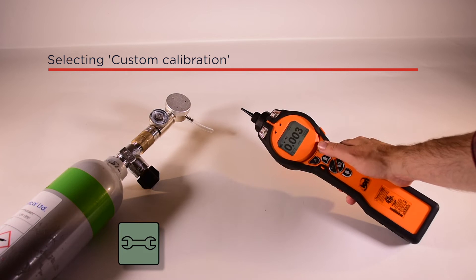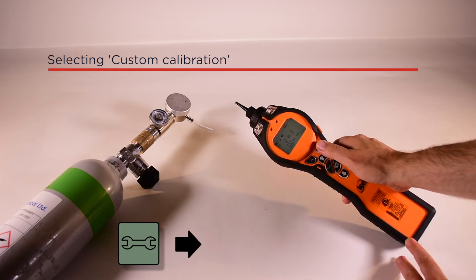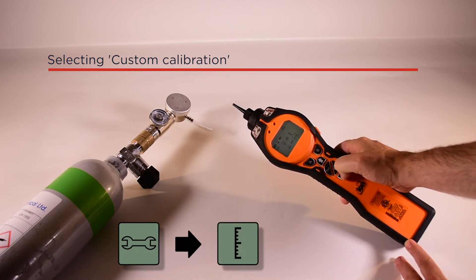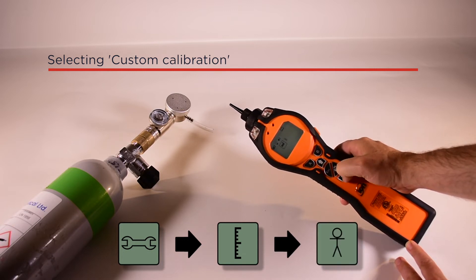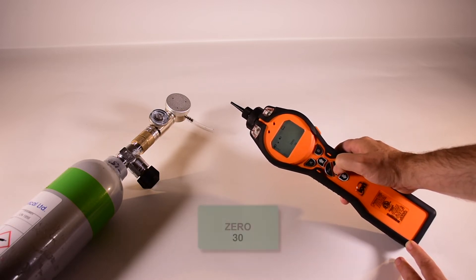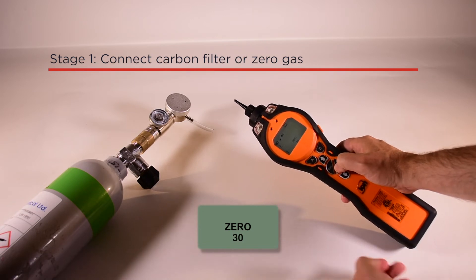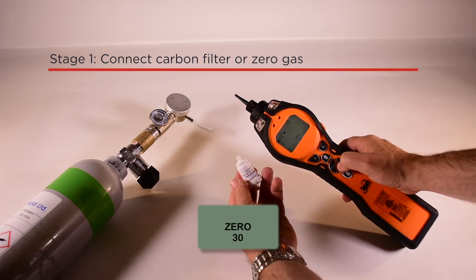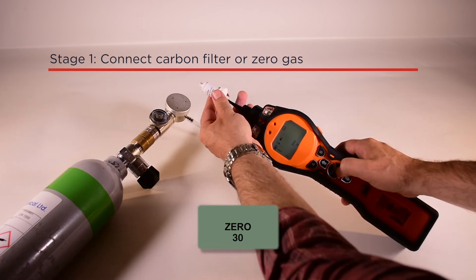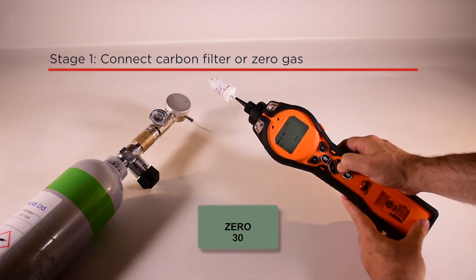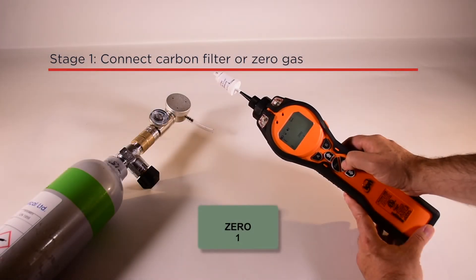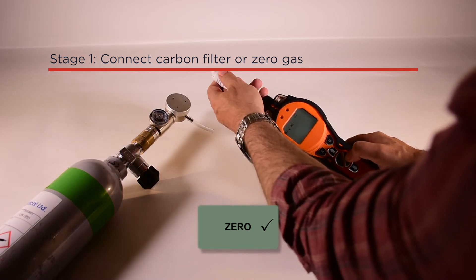Select options, calibration, and then custom calibration. When zero appears, connect your carbon filter and press enter. A 30-second timer will count down and then a check mark appears to indicate the zero stage is complete. Press enter. Now disconnect the carbon filter.